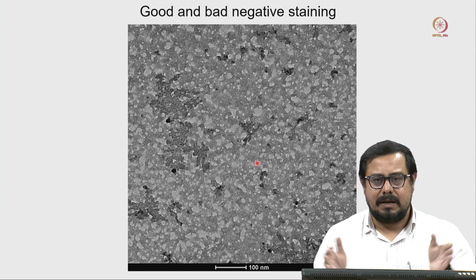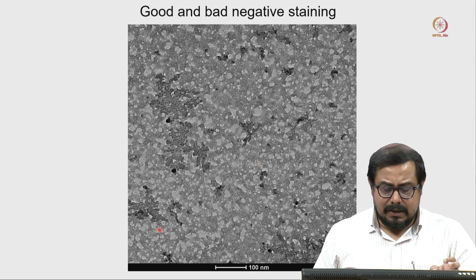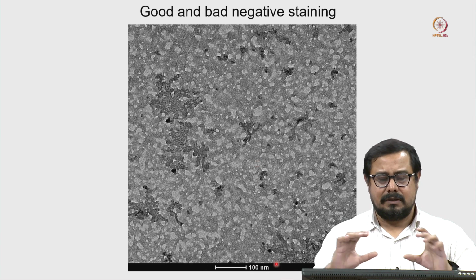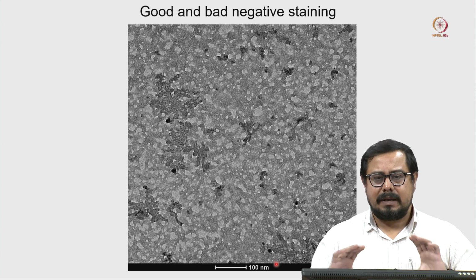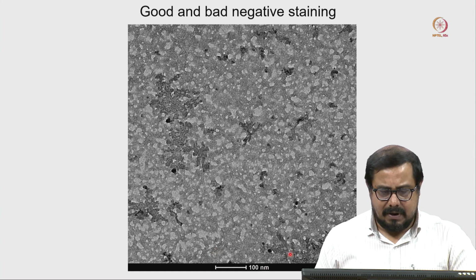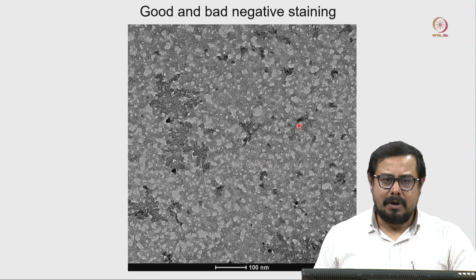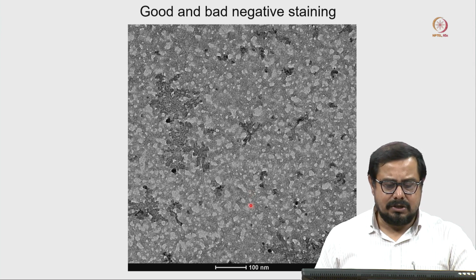Sometimes those things will be a little bit variable. That is the reason most of the time we use a scale bar that is calibrated based on our microscope and camera position. This calibrated magnification appears as a scale bar in your micrograph. So whenever you show any TEM images or cryo-EM images, don't forget, always keep the scale bar. It may be in the nanometer range or micrometer range, and this will vary based on your magnification.